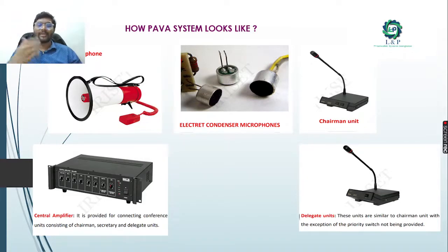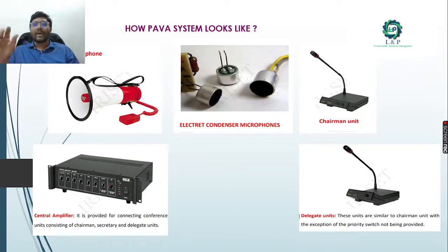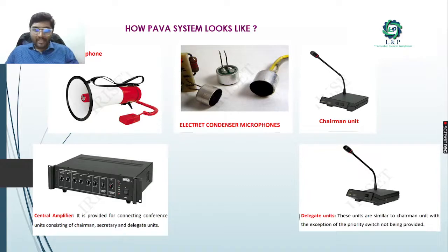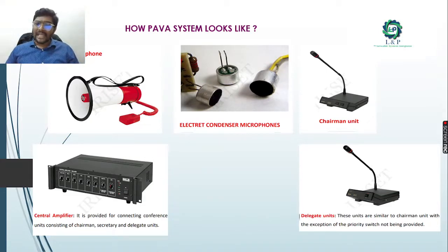We also have power megaphones, condenser microphones, and a chairman unit used in the main control room. The chairman unit has a switch provision - when pressed and talked into, it is given the highest priority. Even if music is playing through the speakers, pressing the chairman unit overrides everything. The local unit does not have this priority switch. Apart from the normal amplifier, we have central amplifiers where the main amplifier acts as master and the central amplifiers act as slaves.